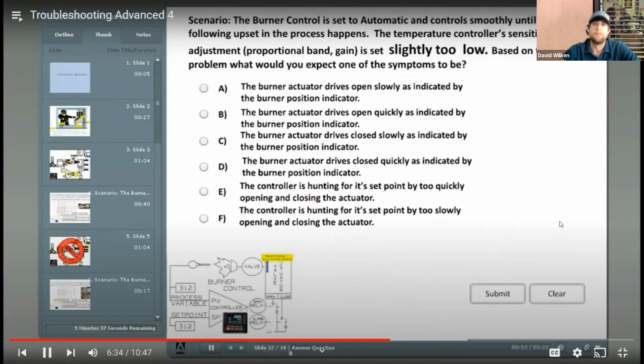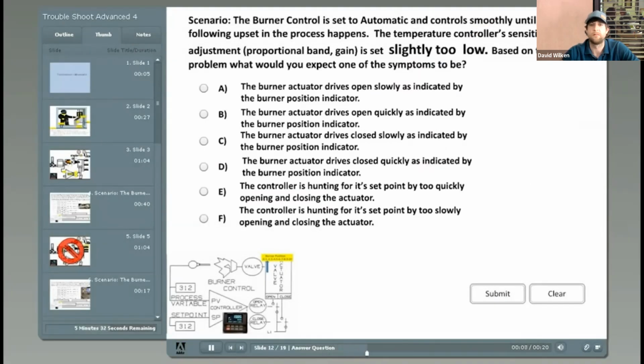Scenario: the burner control is set to automatic and controls smoothly until the following upset in the process happens. The temperature controller's sensitivity adjustment, proportional band gain, is set slightly too low. Based on this problem, what would you expect one of the symptoms to be? What do you think, Isaac? Sensitivity slightly too low. Slightly too low, so it's slowly gonna open. I think we're gonna get some hunting because it's gonna be slightly too slow in both directions.